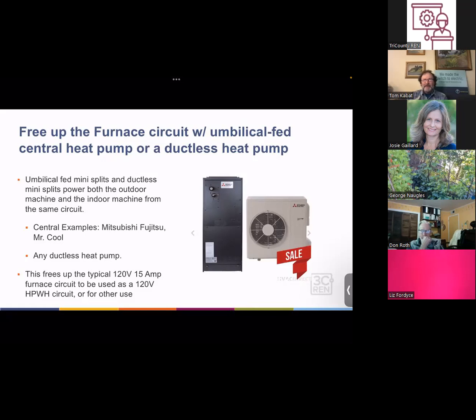And then the heat pump's got plenty of time to recharge all that water, because I don't really need to stand by and watch my water heater heat up. All I need to get done is meet my peak water heating needs. And so yeah, I definitely recommend upsizing the tanks. What do you give up with going to a lower power water heater? It just can't peak as fast, or it doesn't finish reheating as fast. So if you had, say, 2 waves of hot water rush hour close together, the second wave maybe would be getting warm water.